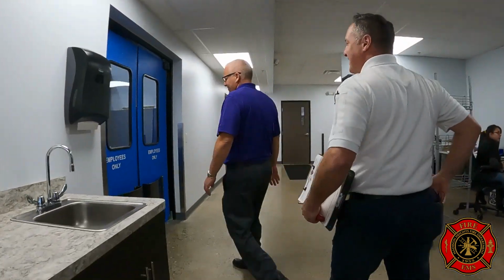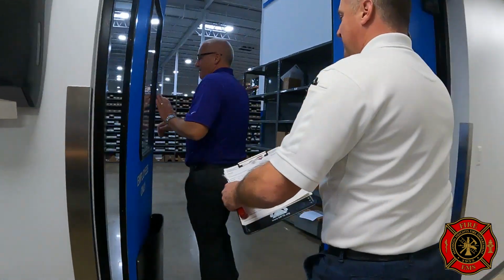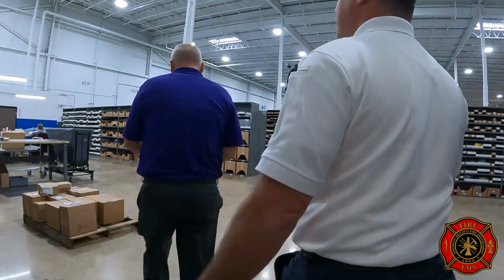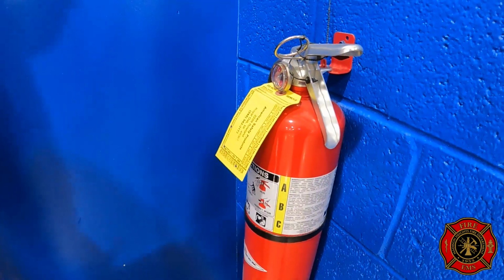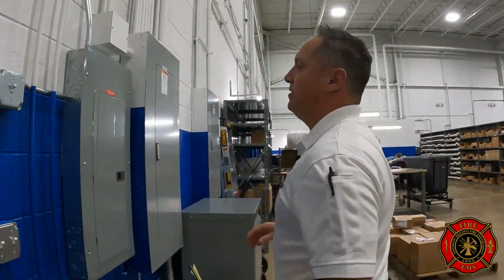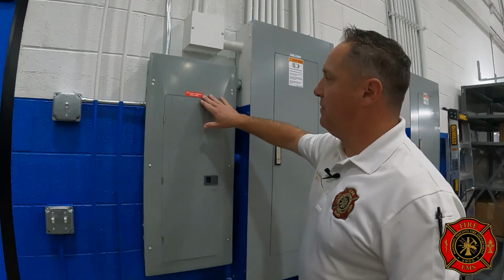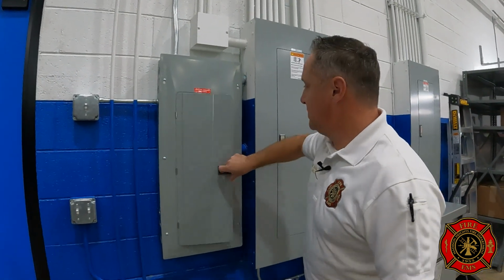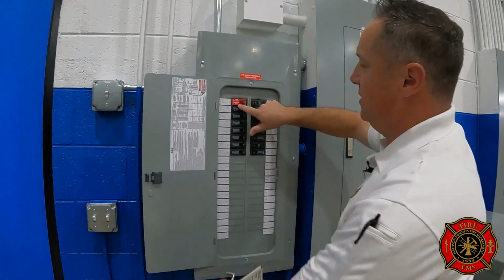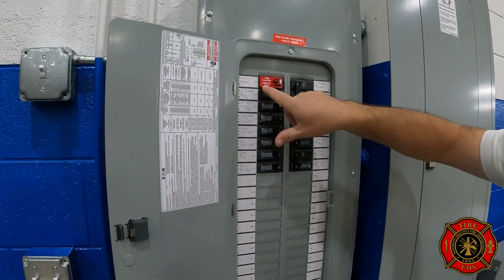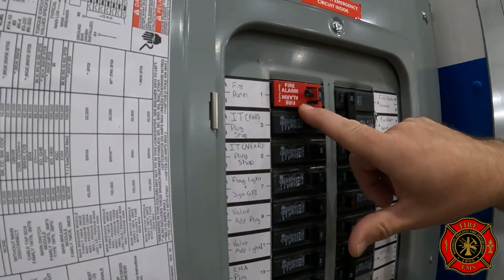Thank you. So some of the things I'm looking for are their fire extinguishers, making sure they're certified annually by a third party every year, making sure that the pressure is still in the green zone, and it is good. I'll look at the electrical system, so I know that the circuit breaker for the fire alarm system is inside this one. I'll make sure it has a lock on it, and it's always a red lock for the fire alarm panel, so that it can never be shut off.